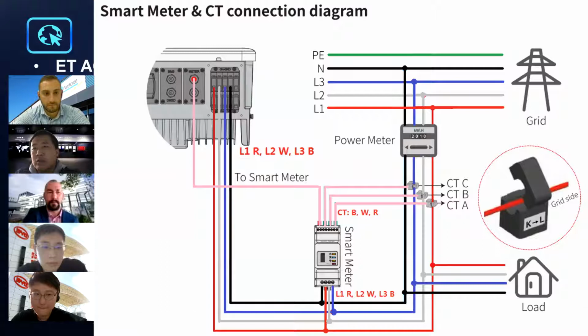For example, at the bottom of the inverter, L1 you connect to the red phase, L2 is the white phase, and L3 is the blue phase. Then at the bottom of your smart meter in your meter box, you have L1, L2, and L3. You also need to connect red, white, and blue phases to these three phase voltage reference points. On the top, you have 3 CT clamps. This is a little bit tricky: the top CT clamp sequence is actually opposite to the bottom one. So for example, you have 1 on red, 2 on white, and 3 on blue at the bottom, and on the top, from left to right, you have blue, white, and red on the CT positions. Just make sure you wire this properly when you install the system. Also, the arrow on the CT clamp points to the grid. So we can jump to the next one, Ramsey, please.